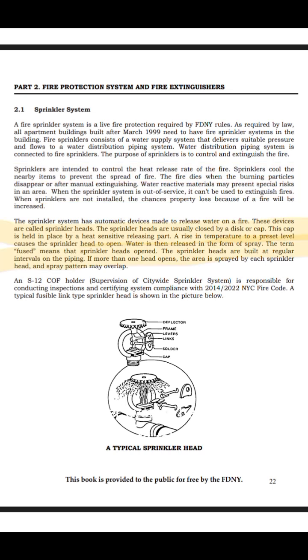The sprinkler system has automatic devices made to release water on a fire. These devices are called sprinkler heads. The sprinkler heads are usually closed by a disc or cap. This cap is held in place by a heat-sensitive releasing part. A rise in temperature to a preset level causes the sprinkler head to open. Water is then released in the form of spray. The term fused means that sprinkler heads opened. The sprinkler heads are built at regular intervals on the piping. If more than one head opens, the area is sprayed by each sprinkler head and the spray patterns may overlap.